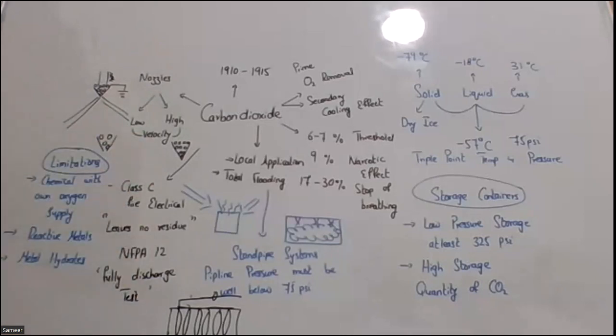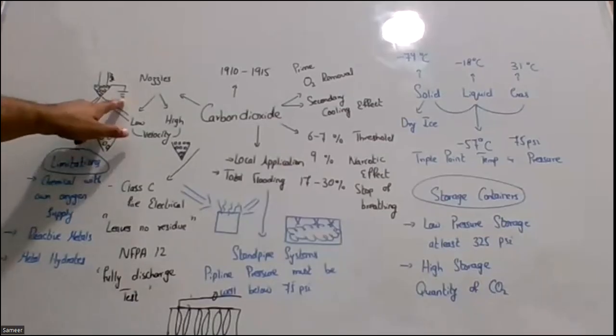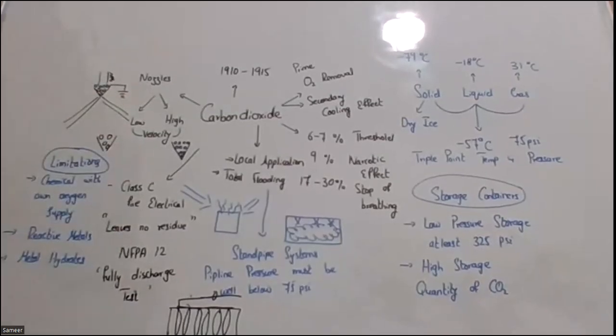All the nozzles must always be grounded for any type of standpipe system, whether it is a dry pipe system, dry chemical powder, carbon dioxide system, clean agent, any type. The nozzles must be grounded, because of the intense pressure, static charges are accumulated on the top of the nozzle.